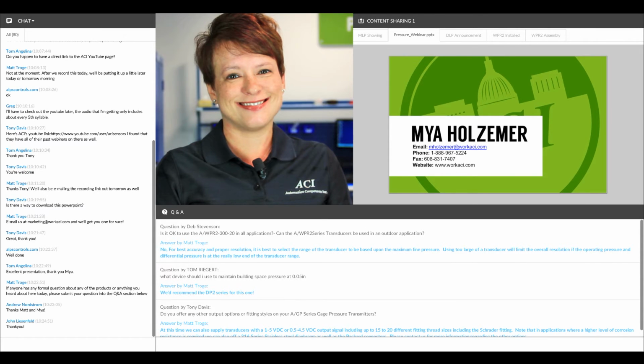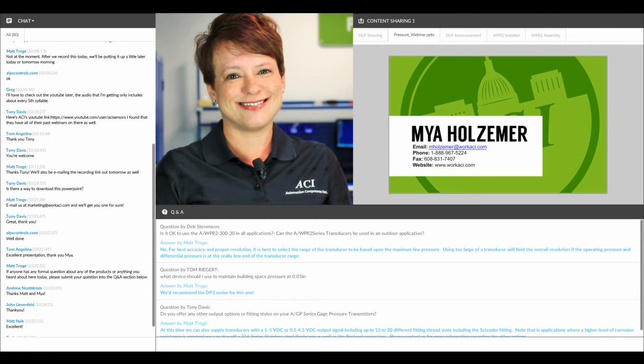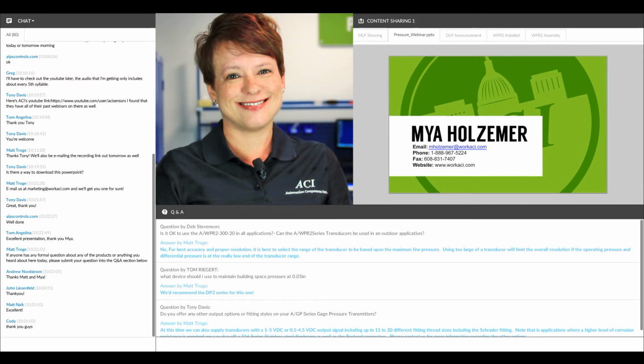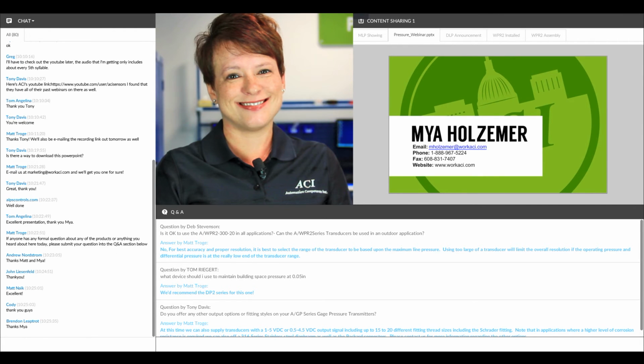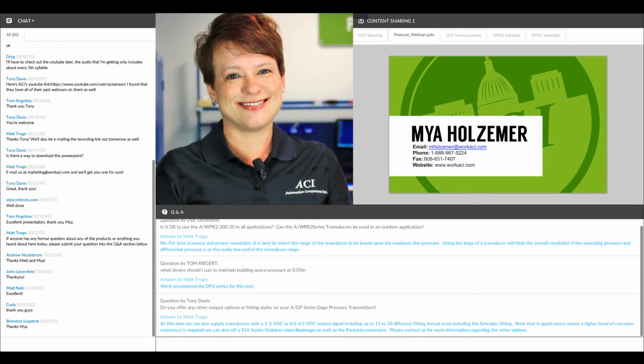I do see a question here from Neil, and I think I'm actually going to let Rob take that one. It's asking, is there a way to get an individual output of both sensors as well as the DP on the WPR2? Like I said, I'll let Rob answer that one more in depth, but from what I believe, the electrical output, meaning the current or the voltage output that you're going to tie into your controller, is going to be the differential between the two. However, if you get the LCD version, you would have access visually to see both what the high side and the low side are doing.